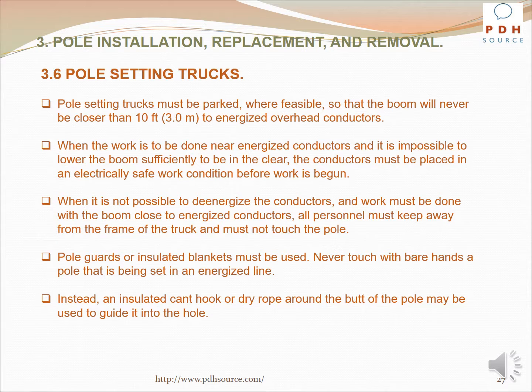Pole setting trucks must be parked where feasible so that the boom will never be closer than 10 feet to energized overhead conductors. When the work is to be done near energized conductors and it is impossible to lower the boom sufficiently to be in the clear, the conductors must be placed in an electrically safe work condition before work is begun. When it is not possible to de-energize the conductors and work must be done with the boom close to energized conductors, all personnel must keep away from the frame of the truck and must not touch the pole. Pole guards or insulated blankets must be used.